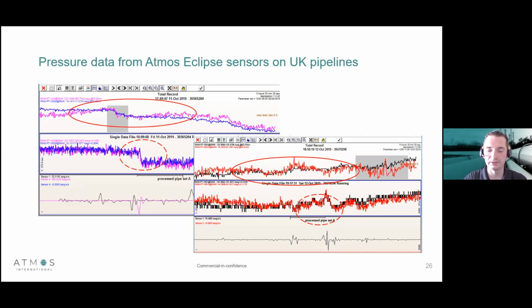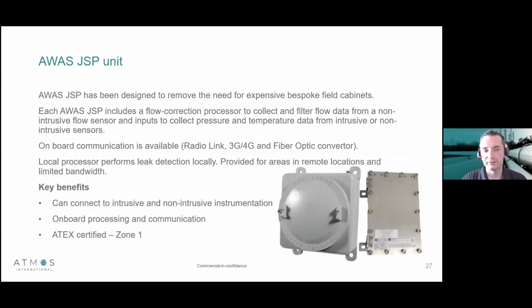The dotted circle is actually showing a small operational change, around 0.3 bar of change, which both sensors are effectively picking up. As well as the Eclipse, we've redesigned the expensive bespoke field cabinets to something far more small and compact, so that we can put these devices in very remote locations with the instrumentation we need. And we use these AWAS JSP units where we might not be able to install an Eclipse because the diameter might be too large or we don't have the space available. And all the communication options are available to us. So we can use radio link, 3G, 4G, and we can even connect to fiber optic if it's available.